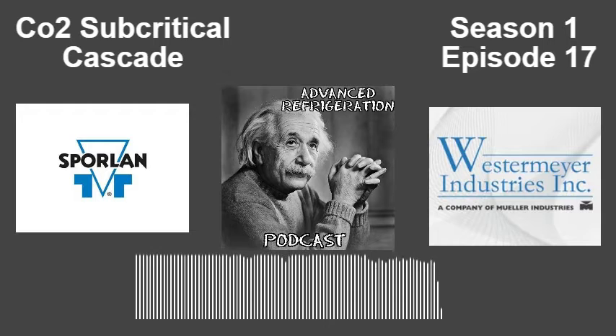Some manufacturers, some Zero Zone racks, some Hussmann racks, want to control about 25 degree CO2. So they have some EPRs on the DX side, either the 448, 449, or 513, and they're trying to control 18 degrees saturated, which, with a 7-degree TD, brings you up to 25 degrees CO2. If you look at the PT chart, once again, that goes up to 450 PSI. And basically that's what we're doing. So it's a lot like pumped liquid CO2. The only difference is that we're actually using compressors to circulate the CO2.